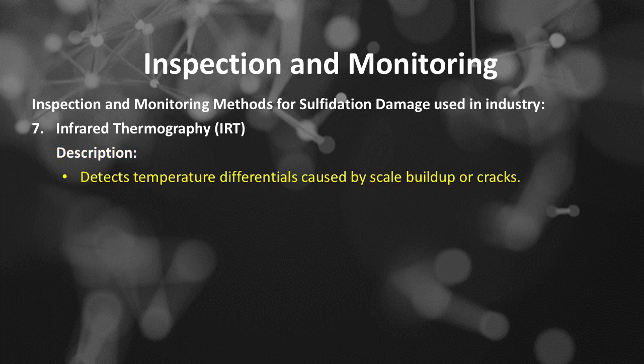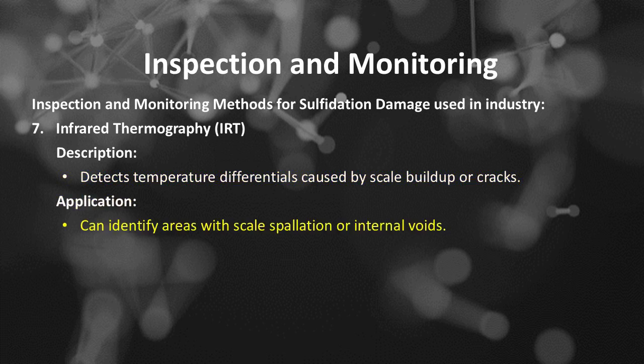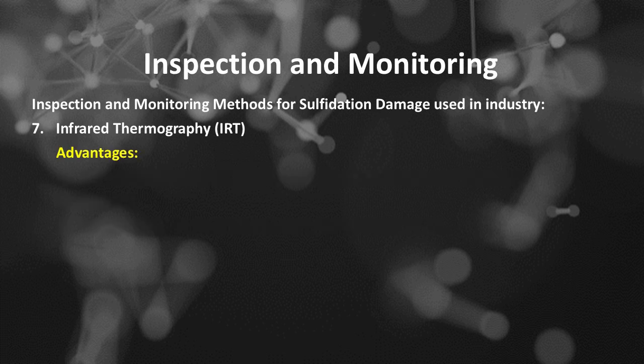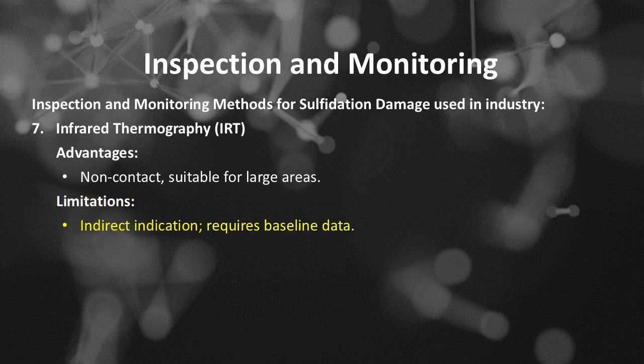Detects temperature differentials caused by scale buildup or cracks. Infrared thermography, or IRT, application: can identify areas with scale spallation or internal voids. IRT advantages: non-contact, suitable for large areas. IRT limitations: indirect indication, requires baseline data, and less effective for internal sulfide detection.